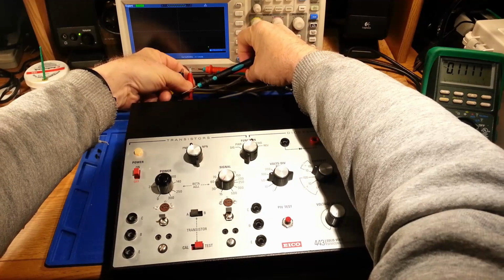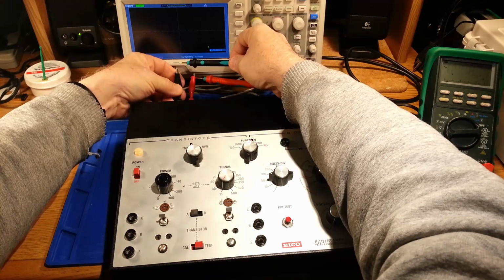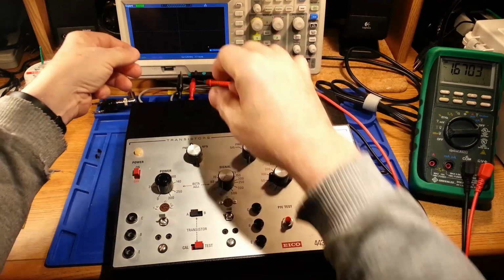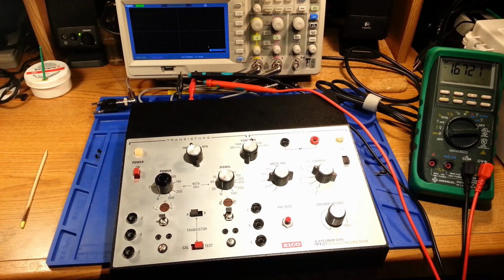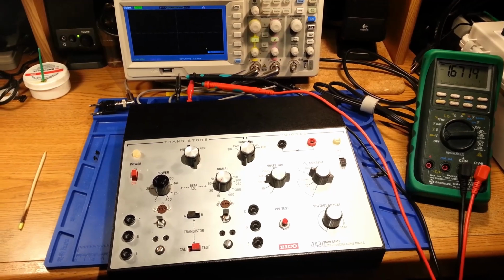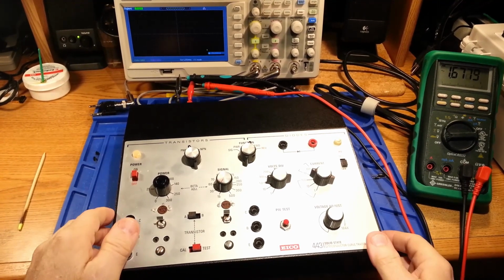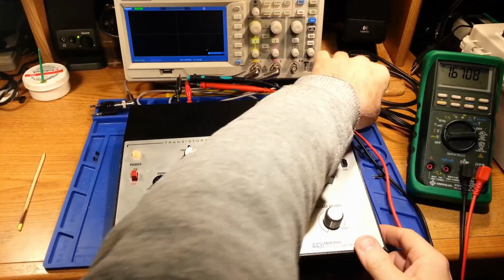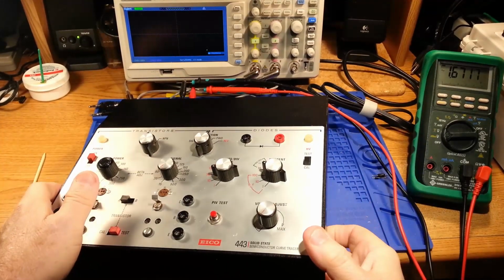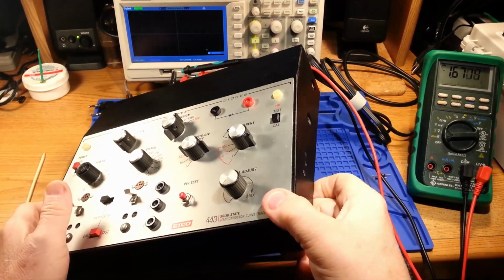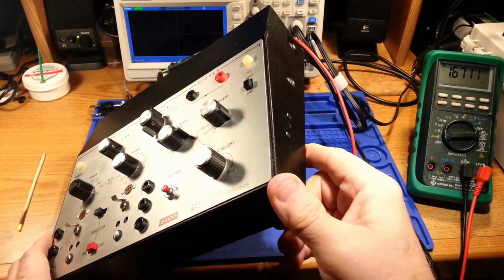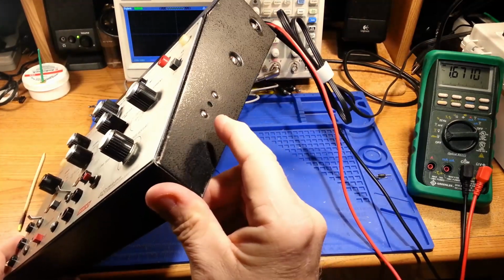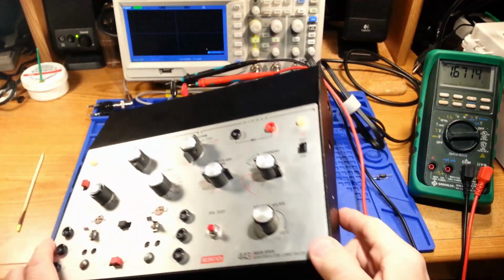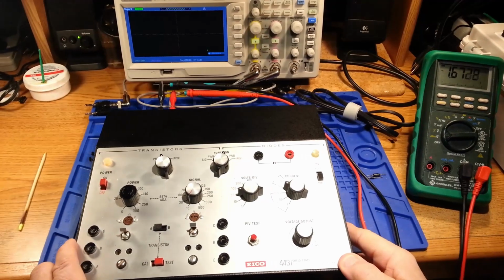And connect them to the digital voltmeter. According to the digital voltmeter, what we have is 1.67 volts, and it says we're supposed to have 1.7. So it says if you don't have the proper voltage, you need to adjust R6. And R6 is that one right there.